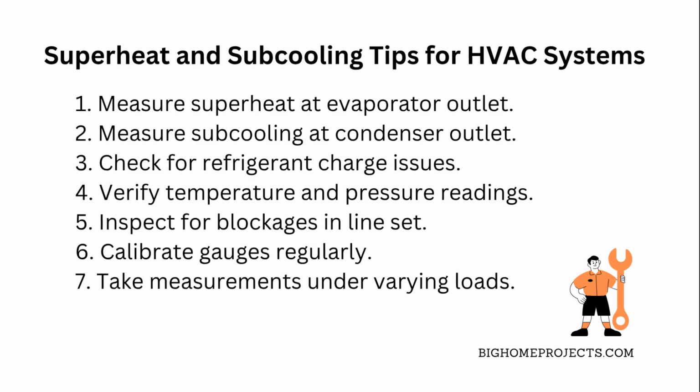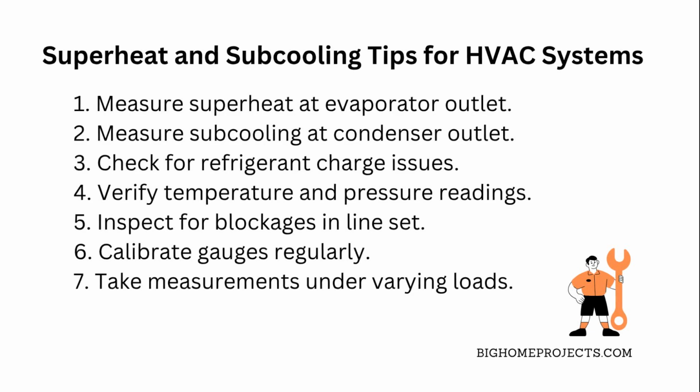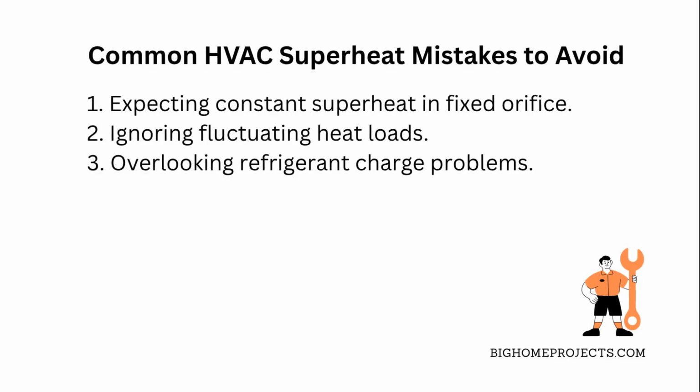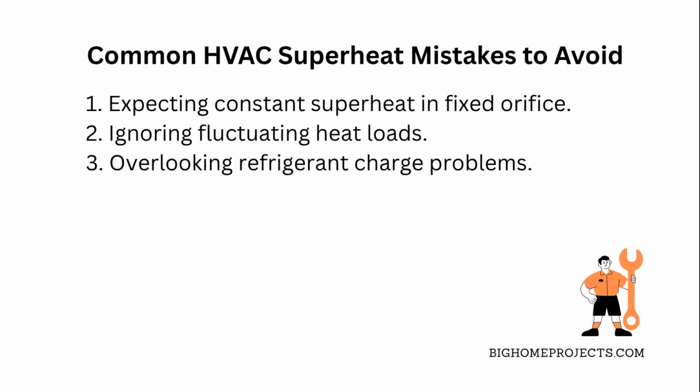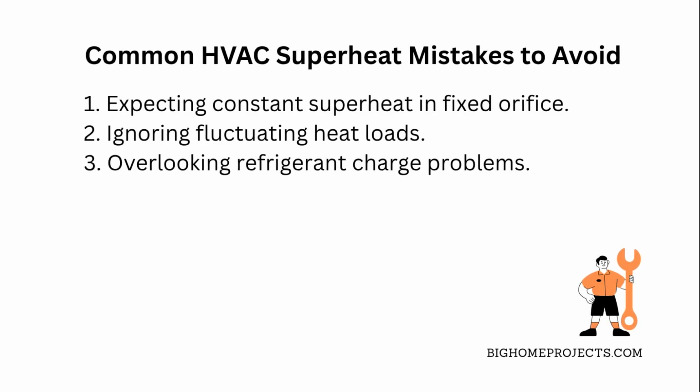Remember, knowing how superheat swings in fixed orifice setups helps you figure out if you're dealing with undercharge, overcharge, or even a failing component. One of the biggest mistakes HVAC techs make when dealing with superheat on fixed orifice systems is assuming superheat should be constant like with a thermostatic expansion valve. It won't be, so you've got to expect some variation and interpret it accordingly.